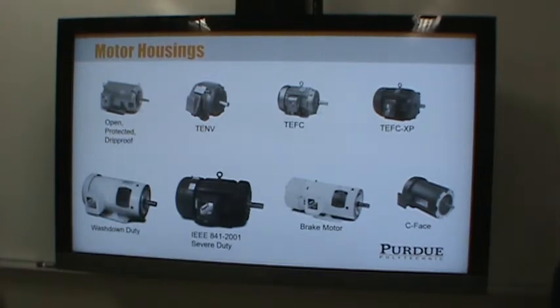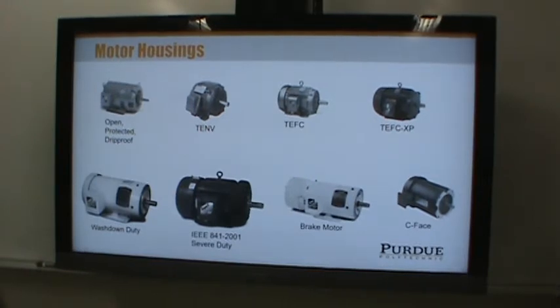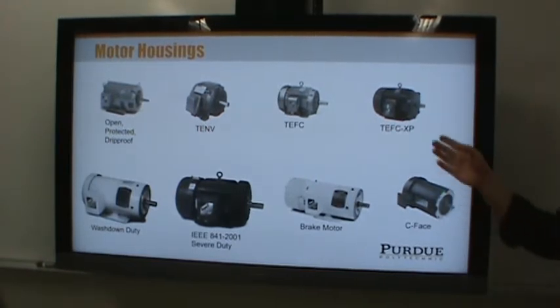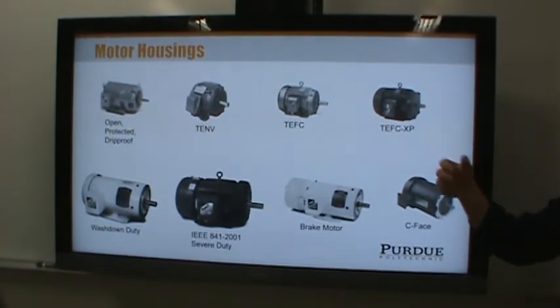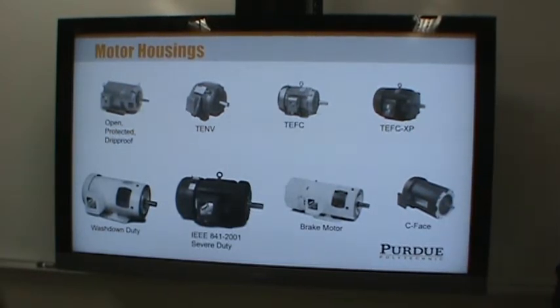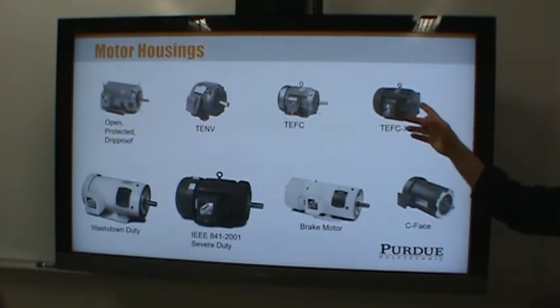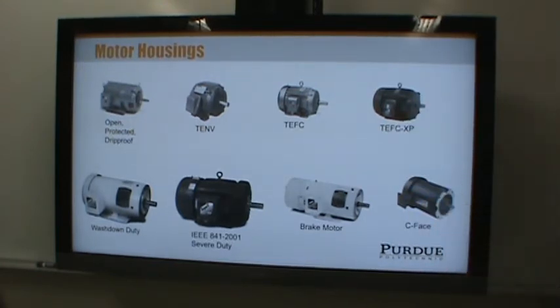If it's totally enclosed, how do you do maintenance? Typically you don't — if the motor stops working you take it out, put another one in, and send the old one to a motor repair shop. Unless the organization is huge and has its own motor shop, they typically don't repair motors in-house. The manufacturer may include a lubrication port if lubrication is intended.